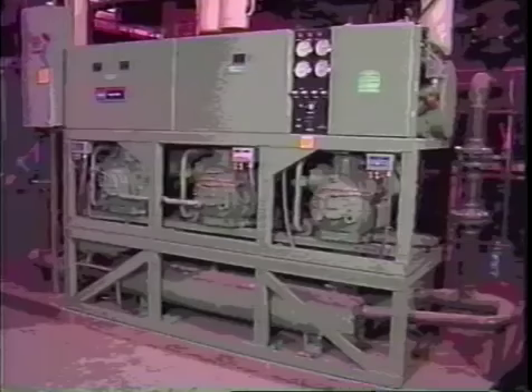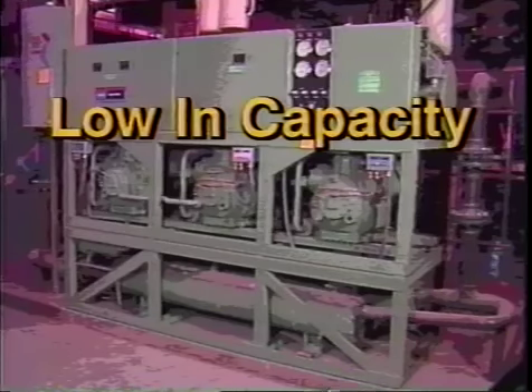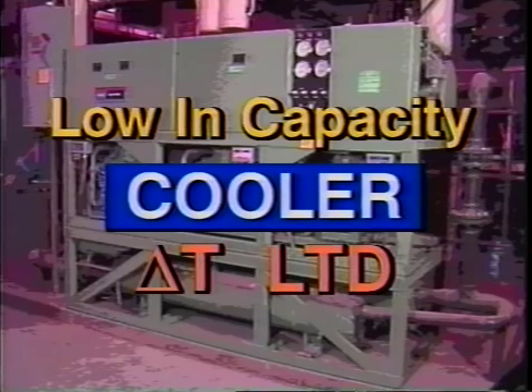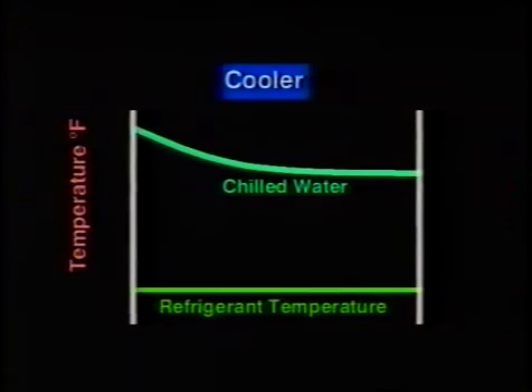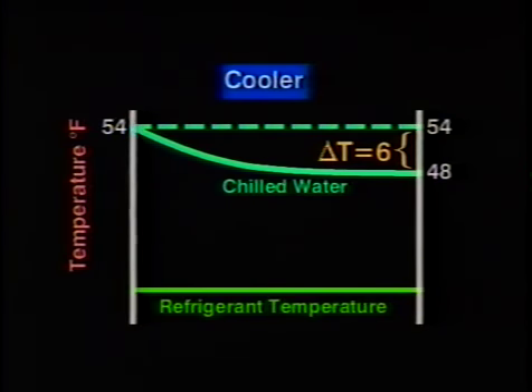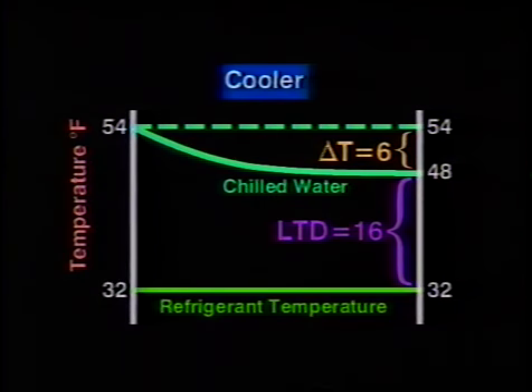In this first example, the system is low in capacity, so we'll want to look at the cooler delta T and LTD. We see that the entering chilled water is normal at 54 degrees Fahrenheit, but the leaving water is 48 degrees, giving us a cooler delta T of only 6 degrees, instead of the expected 10 degrees, and the system is not adequately carrying the load. The saturated cooler temperature is low at 32 degrees, and from the approach curve, we see that the LTD is high at 16 degrees instead of the expected 8 degrees.